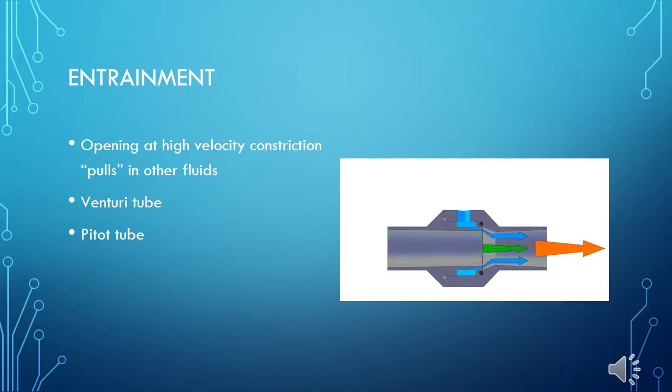When the opening's smaller, the oxygen concentration getting to the patient is going to be a little bit higher. When it's bigger, there's more air getting pulled in from atmosphere, so the oxygen concentration is going to be a little bit lower. It's just interesting to understand when you're playing with that device, that's what's actually going on. That's the magic behind it.